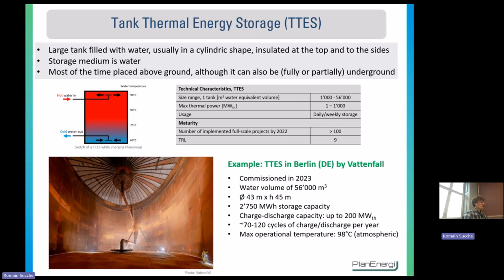One example was chosen by the task 39, which is a TTES in Berlin, in Germany, by Vattenfall, that was commissioned in 2023 with a water volume of 56,000 cubic meters and a storage capacity of 2,750 megawatt hours, and very highly utilized because the storage charge and discharge cycle was quite high, 70 to 120 cycles per year.